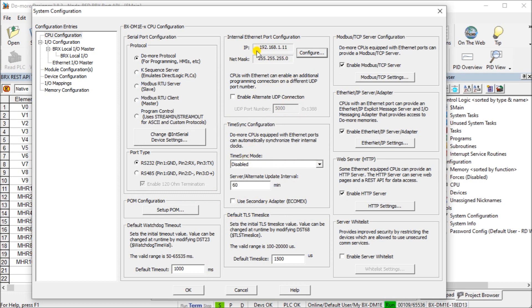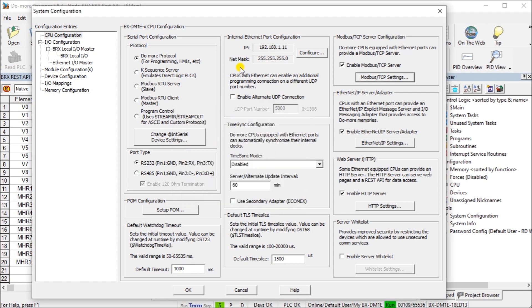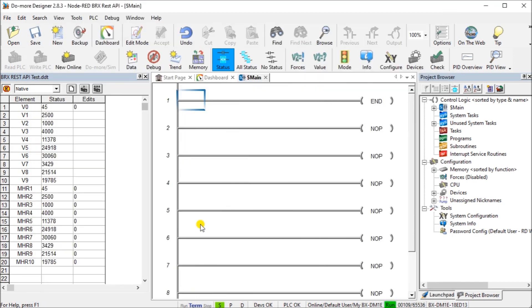The only other thing to do is actually look at our Modbus TCP server as well. Because since we're going to be writing to this controller, we have to enable our Modbus TCP server. Now it is enabled by default. If we look at the settings, you'll see here that we have our maximum settings of four, our client activity timeout. I've set for 3,600. It defaults to 60 seconds. Then our default port is 502, which is the same for all Modbus TCP.